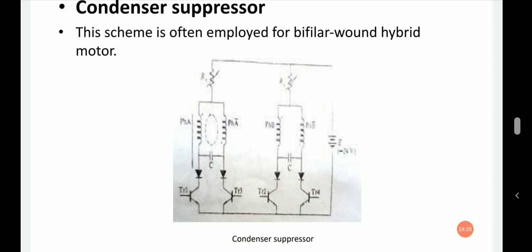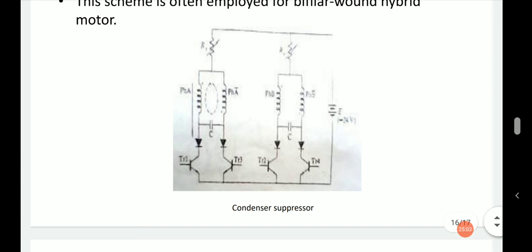However, if a current path is not provided or a high resistance is connected, no current will be caused by this EMF. When the condenser is connected between phases, an oscillatory current will flow in the closed loop and Joule heat is generated in the windings, which means the condenser works as an electrical damper.